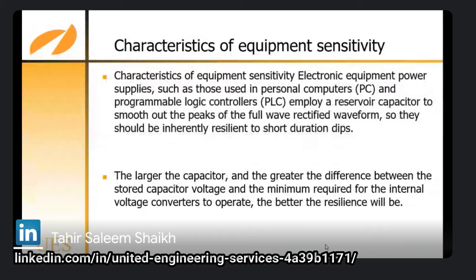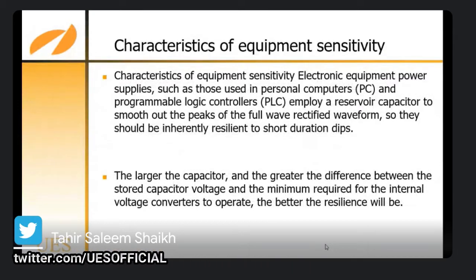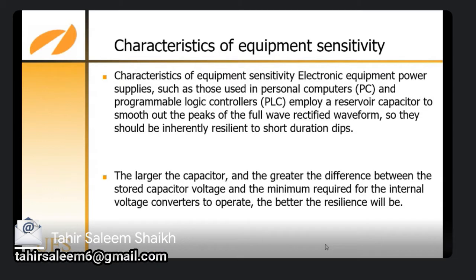Characteristics of the equipment: sensitive electronic equipment power supplies, such as those used in personal computers and programmable logic controllers, employ a reservoir capacitor to smooth out the peaks of the full wave rectified waveform. So there should be inherent resilience to short duration dips. The larger the capacitor, the greater the difference between the stored capacitor voltage and the minimum required for the internal voltage converters to operate, and the better the resilience will be.